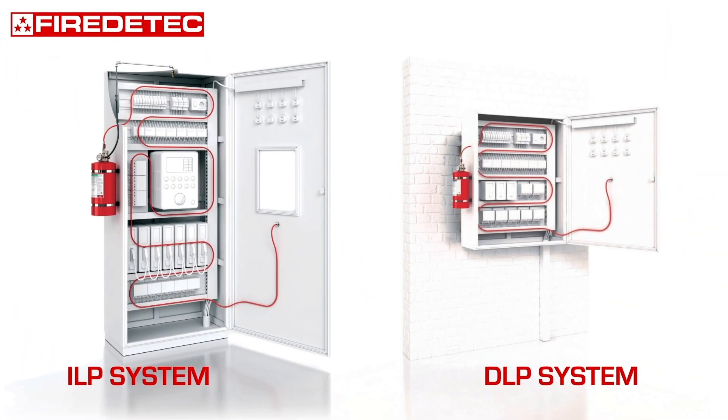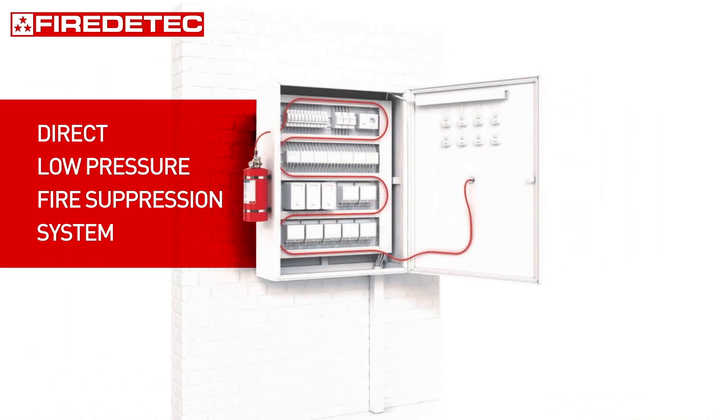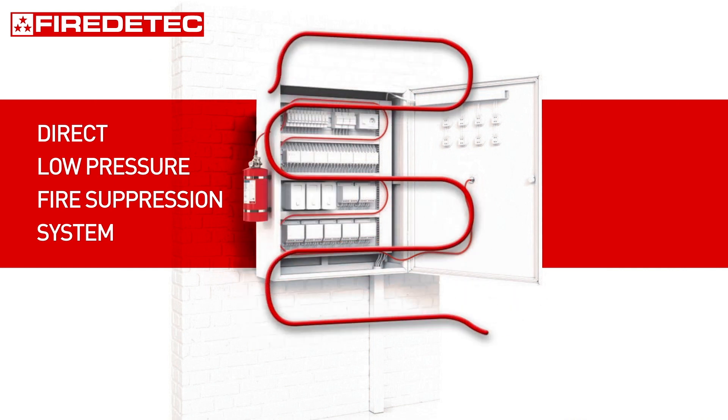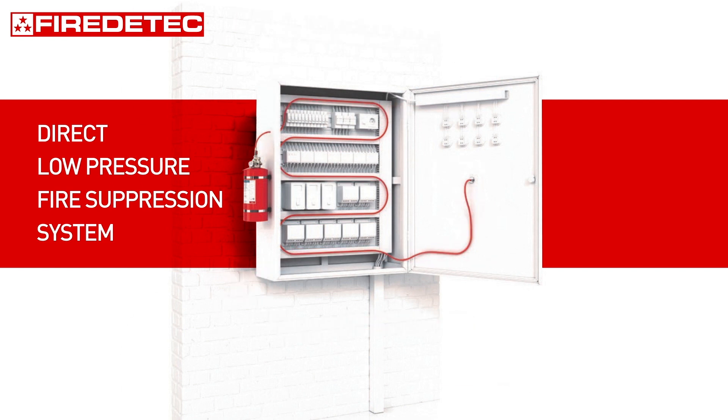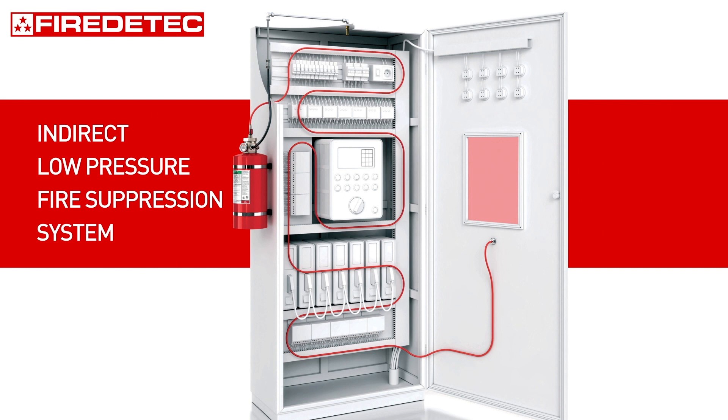FireDETEC systems are available in indirect and direct low pressure configurations. The direct low pressure system consists of a cylinder filled with Novec 1230 fluid and a FireDETEC pneumatic detection tube pressurized with 16 bar nitrogen. It is specifically designed to protect small enclosures up to 2 cubic meters.